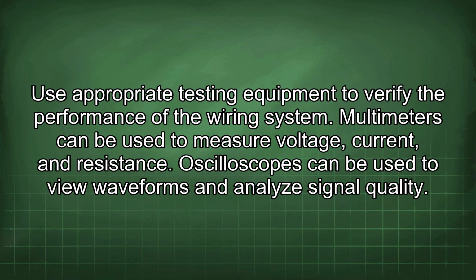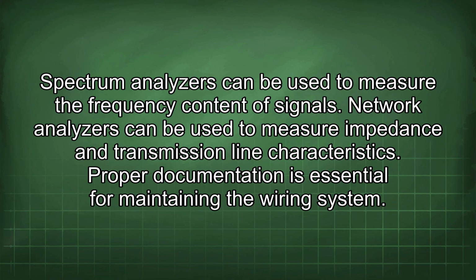Use appropriate testing equipment to verify the performance of the wiring system. Multimeters can be used to measure voltage, current, and resistance. Oscilloscopes can be used to view waveforms and analyze signal quality. Spectrum analyzers can be used to measure the frequency content of signals. Network analyzers can be used to measure impedance and transmission line characteristics.